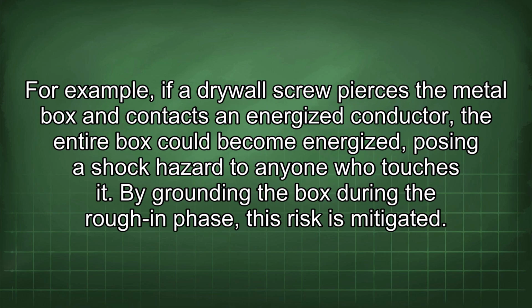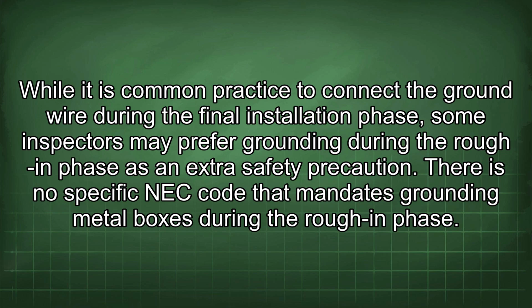For example, if a drywall screw pierces the metal box and contacts an energized conductor, the entire box could become energized, posing a shock hazard to anyone who touches it. By grounding the box during the rough-in phase, this risk is mitigated. While it is common practice to connect the ground wire during the final installation phase, some inspectors may prefer grounding during the rough-in phase as an extra safety precaution.